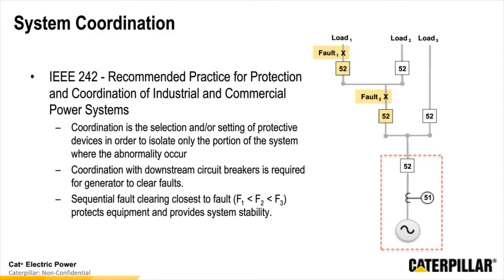Now, if the fault was to move up the system a little bit higher into the next protective zone, we would see that the fault now occurs. We want to clear the next level up 52. So now we would drop loads 1 and 2, and we would continue to power load 3 in this instance. And if the fault was to occur directly outside the generator, we would need to trip the generator circuit breaker. This would drop power to all the loads. But overall, now we're protecting the generator and the asset and the investment that we have made.